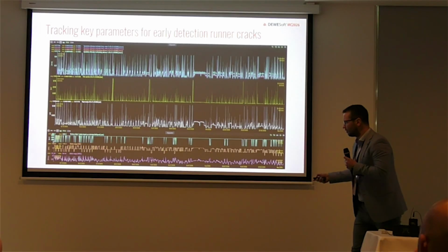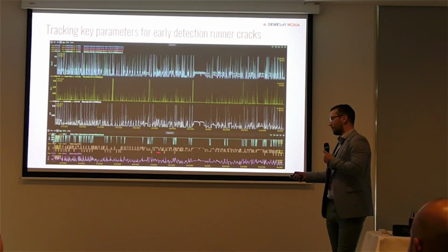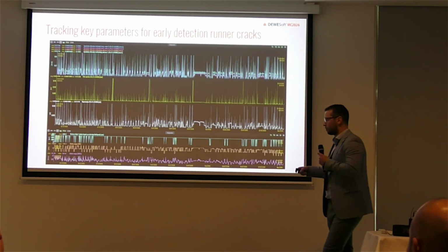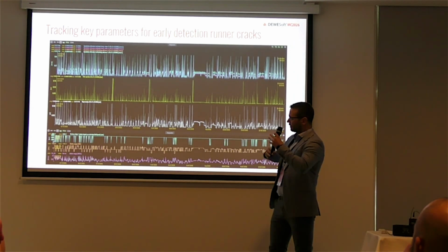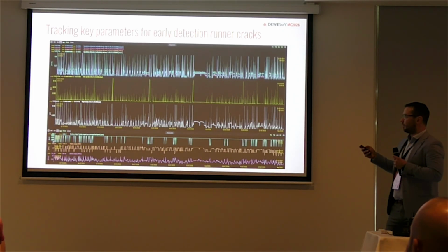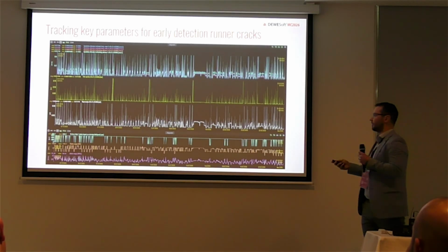This is, I think, 2 or 3 months of data, and you can see that the active power goes up and down, and also the reactive power. So this unit goes through various operating conditions. Now we track it, and we believe that we will now know much earlier that something is starting to happen, before the root cause is completely removed.